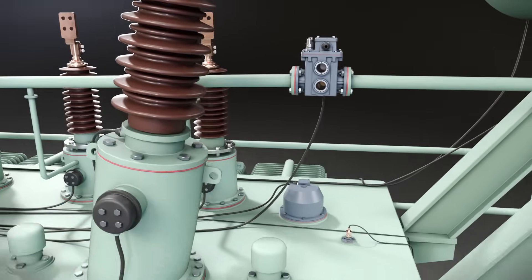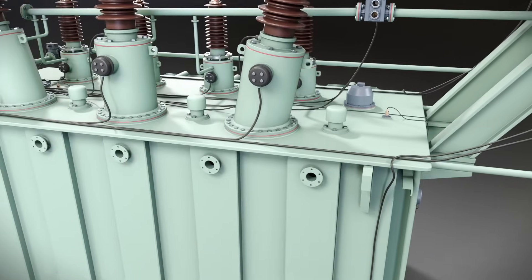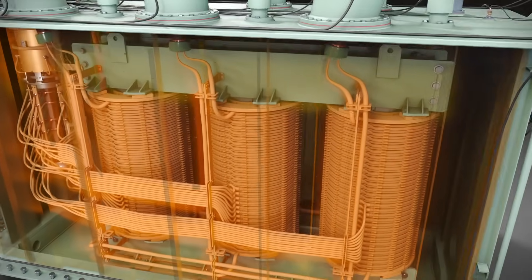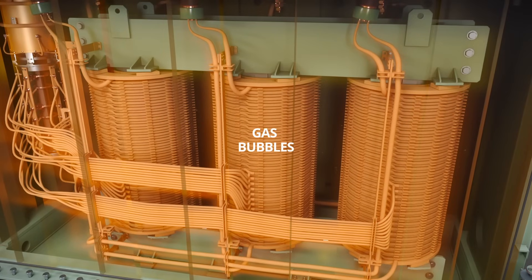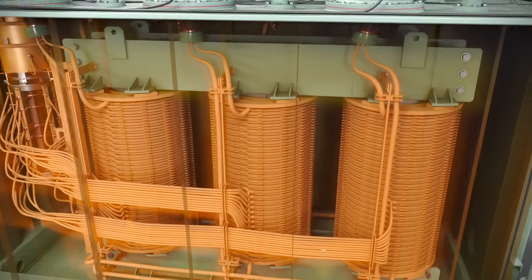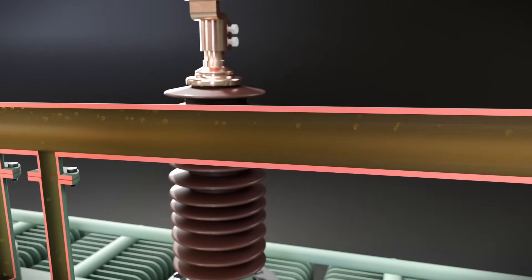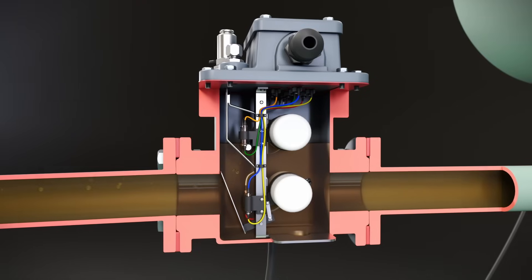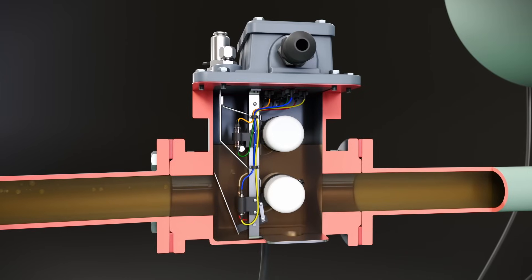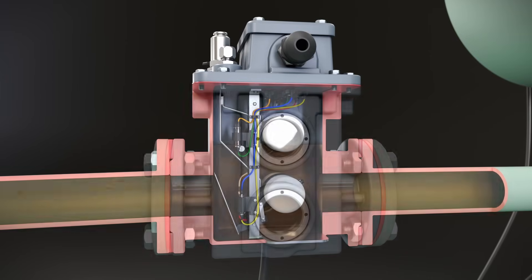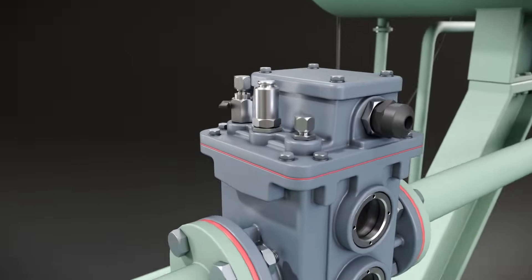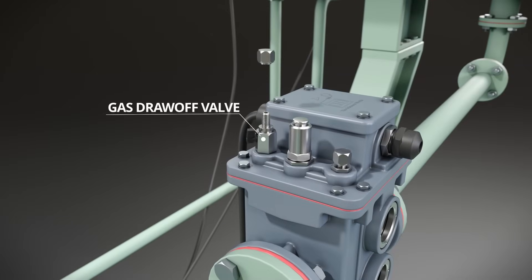During transformer operation, heat generated due to the resistance of the windings causes the decomposition of the surrounding oil and paper insulation, producing gases such as hydrogen, methane, and acetylene. These gas bubbles rise in the transformer tank and move toward the conservator through the connecting pipeline. Once the gas bubbles reach the Buchholz relay, they accumulate in its housing. This collected gas can be extracted through a gas draw-off valve and analyzed to assess the insulation health of the transformer.